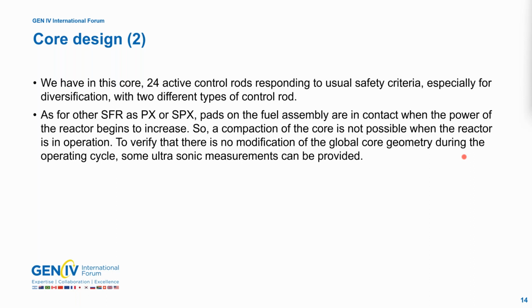Always on the core design, we have in this core 24 active control rods responding to the usual safety criteria, especially for diversification with two different types of control rod. As for the other sodium fast reactors, the pads on the fuel assembly are in contact when the power of the reactor begins to increase, so compaction of the core is not possible when the reactor is in operation. And to verify that there is no modification of the global core geometry during the operating cycle, some ultrasonic measurement can be provided to survey the geometry of the core.